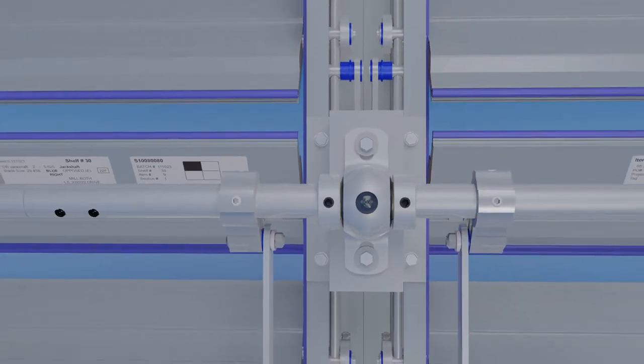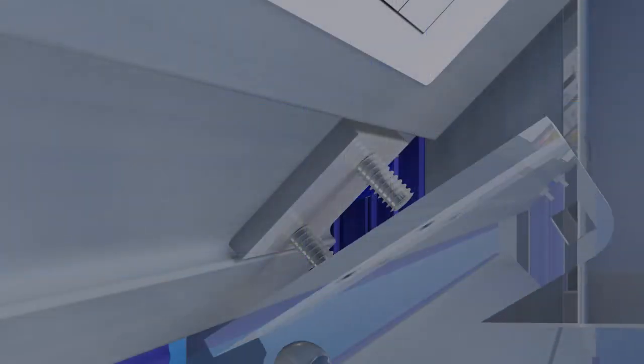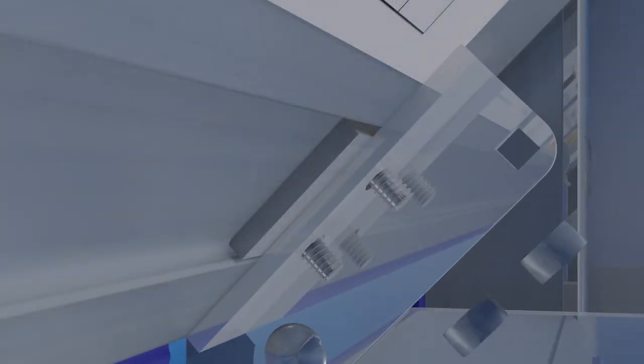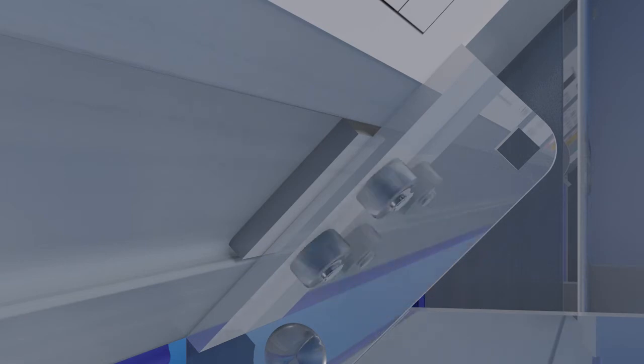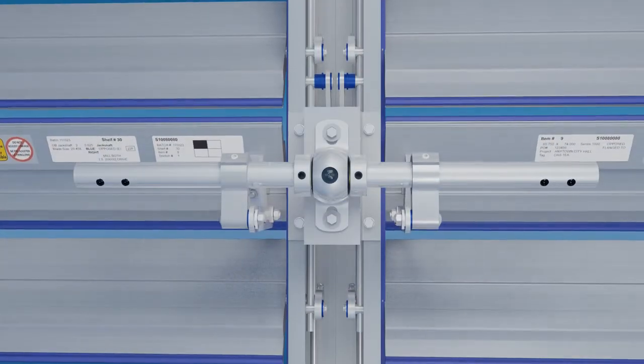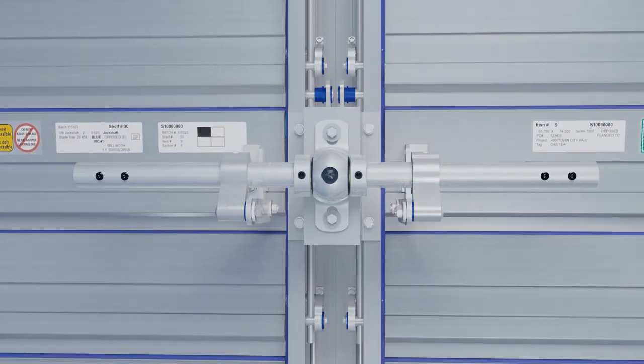It is important to ensure that the U-bolts do not fall out the back of the damper blades. Retighten the hex nuts on both U-bolts, securely fastening the blade clips to the damper blades. Rotate the damper blades back to the closed position.